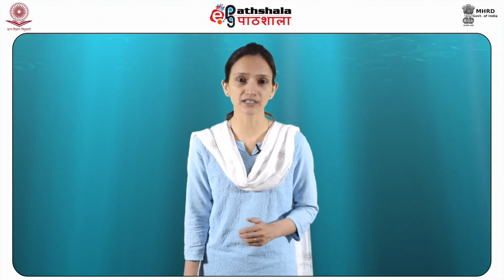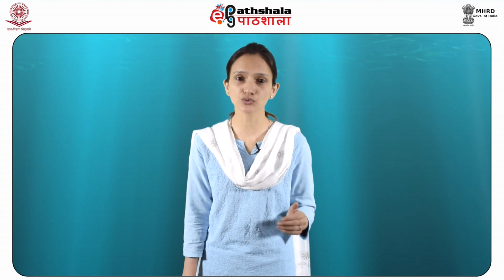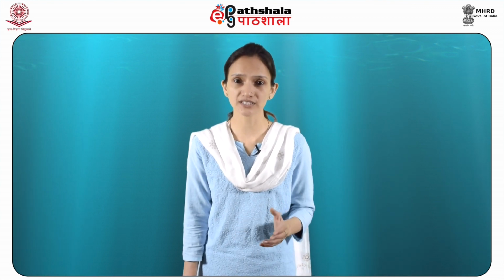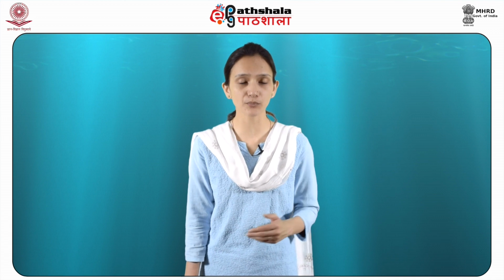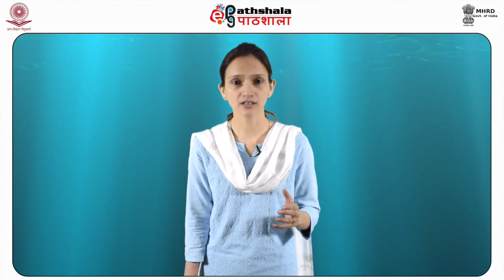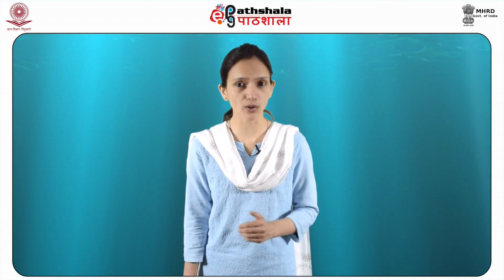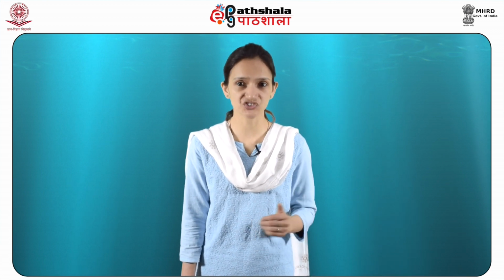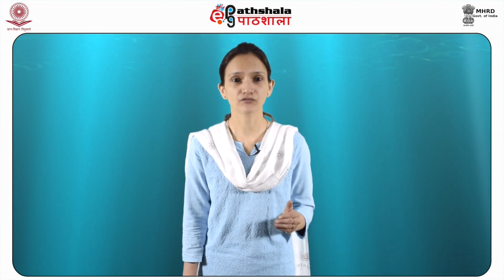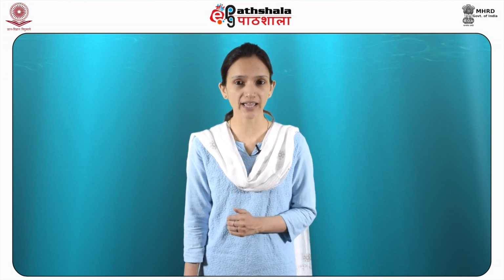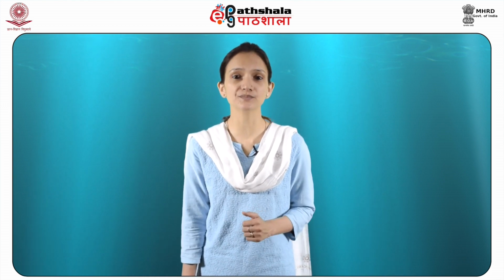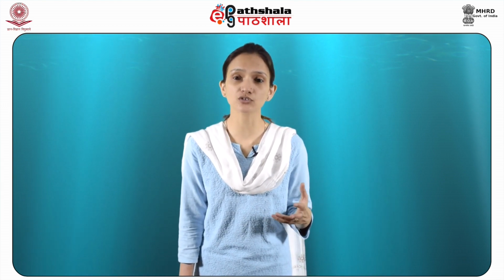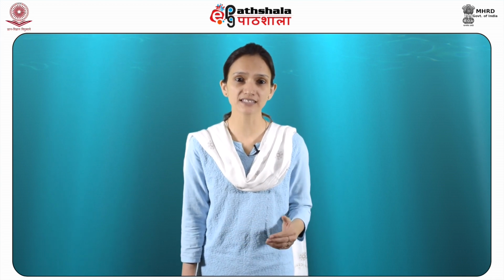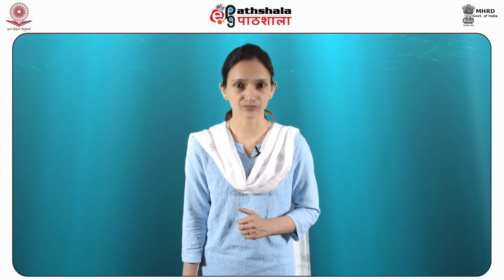The stereoscopic microscope is two compound microscopes mounted side by side in a similar body converging towards the object, having a split optical system for each eye. Both eyes view the same field from different angles and stereoscopic vision thus results. The convergence of the two optical systems is roughly the same as the normal convergence of the eyes when reading or writing.